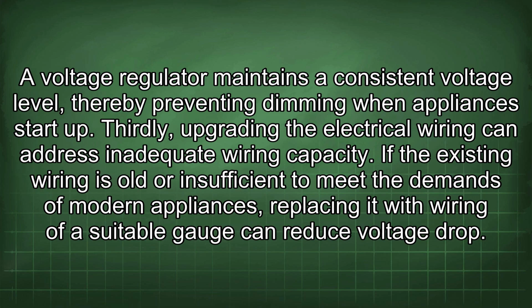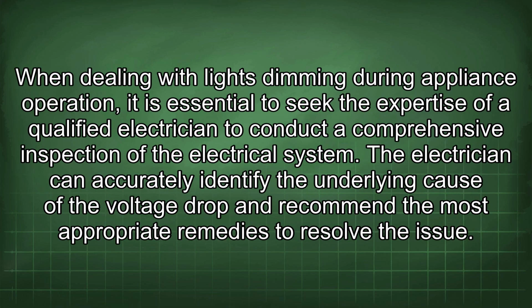Thirdly, upgrading the electrical wiring can address inadequate wiring capacity. If the existing wiring is old or insufficient to meet the demands of modern appliances, replacing it with wiring of a suitable gauge can reduce voltage drop. When dealing with lights dimming during appliance operation, it is essential to seek the expertise of a qualified electrician to conduct a comprehensive inspection of the electrical system. The electrician can accurately identify the underlying cause of the voltage drop and recommend the most appropriate remedies to resolve the issue.